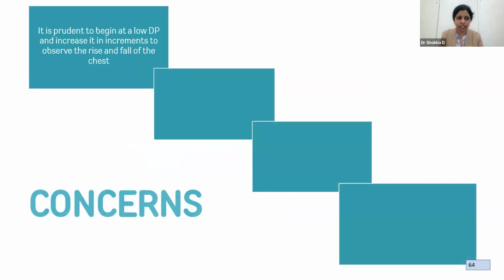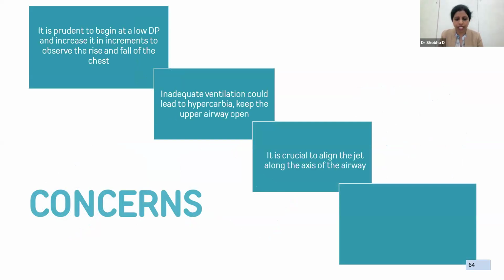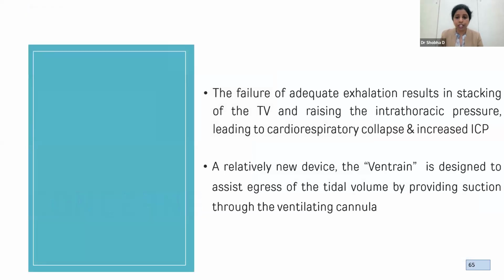So what are the concerns? It's prudent to begin at a low driving pressure and increase it in increments to observe the rise and fall of the chest. Inadequate ventilation could lead to hypercarbia, so keep the upper airway open. It's crucial to align the jet along the axis of the airway. If not, it leads to subcutaneous emphysema and pneumomediastinum. The failure of adequate exhalation results in stacking of the tidal volume and raising the intrathoracic pressure, which leads to cardiorespiratory collapse and also causes an increase in ICP. One solution is the Ventrain, which brings about active expiration.